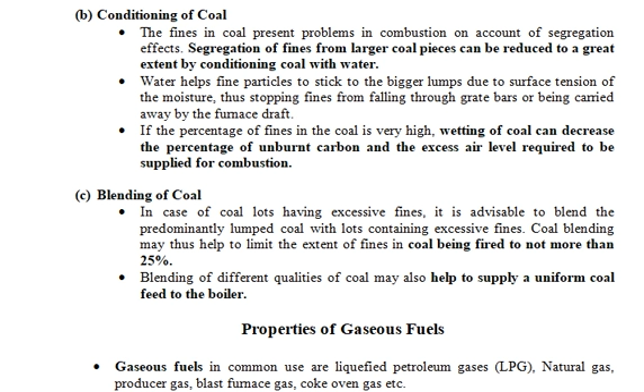Water helps fine particles stick to the bigger lumps due to the surface tension of the moisture. Thus it stops fines from falling through the grate bars or being carried away by the furnace draught. If the percentage of fines in the coal is very high, wetting of coal can decrease the percentage of unburned carbon and the excess air level required to supply for combustion.